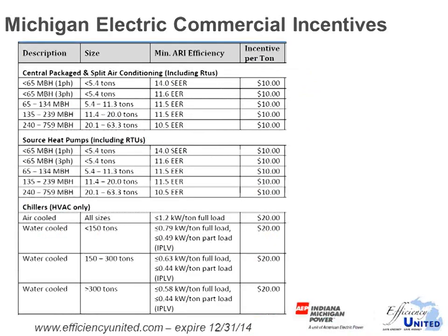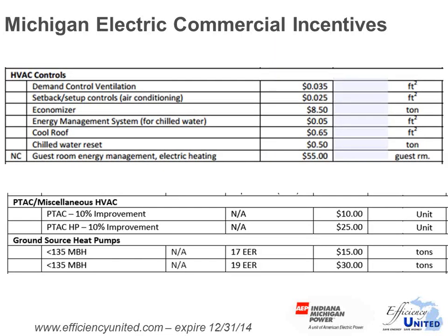and things like that. On the electric side in Michigan, there are also rebates. Basically, they're $10 per ton for going with higher efficiency SEER or EER equipment. There are rebates for heat pumps, also 10 bucks a ton for going with higher efficiency as well. Chillers, it's 20 bucks per ton. You have to hit a certain full load and a certain part load requirement, and it's based on the tonnage of the machine. So if we've got a water-cooled machine greater than 300 tons, you've got to hit 0.58 kW per ton full load, 0.44 kW per ton part load, and then you get a $20 per ton rebate.